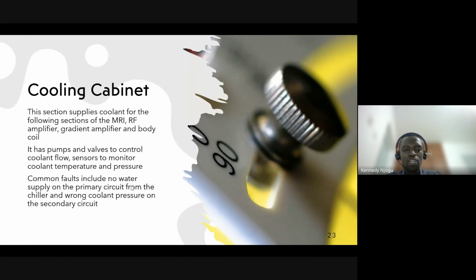So basically some components can be air cooled or water cooled. You check the quality of the air and water, and also the flow and pressure of the water. For us, we monitor the flow and temperature, but pressure is also key - the rate at which water is flowing, measured in liters per minute or liters per hour, or sometimes gallons per minute. They're all the same - you ensure the flow is okay and the pressure is okay.